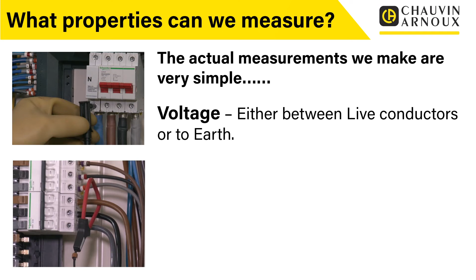So let's take a look at what properties we can measure. Often people get confused with power quality measurement, and they hear all these terms like harmonics and power factor and things like that, and they assume that there's a different test instrument and different connections to measure different things. And actually, it's a lot more simple than that. What we're actually measuring when we measure power quality is voltage, either between live conductors or to earth, and current, either at the incoming supply or for an individual circuit, or maybe even for an individual piece of equipment. So from the voltage and the current measurements, we plot these against another important factor, which is time. And then from those, all of the other values we talk about can be derived.